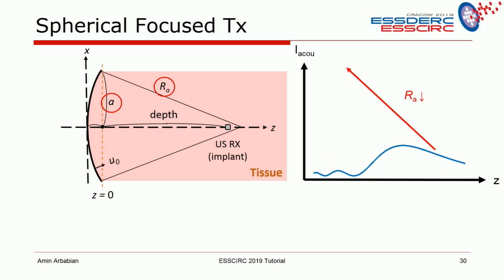So we have a radius of a transducer. We also have a radius of focus. As you can see, as I bring my focus closer and closer in, the focus efficiency goes up because I'm getting a larger effective aperture, or I'm getting a smaller F number. So as you get closer to the transducer, the focusing gets better. And you can see that in optics it's the same thing. As you get closer to your aperture, you can do better focusing. So this is the second effect you see.